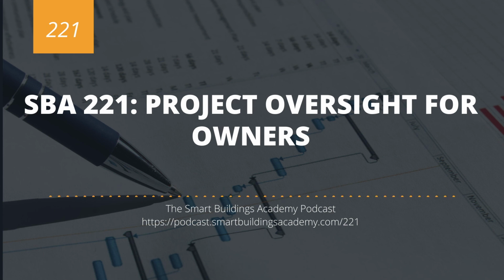That being said, once you understand what is supposed to be done, now you start to go through it. This is where you can request point-to-point documents and you can validate them. You can request functional test sheets and you can validate them. You can work alongside the commissioning agent and validate that systems are actually functioning. This is where I recommend doing document reviews, ensuring that red lines are properly managed and that those red lines are being gathered, properly sourced, and represent what is actually installed in the field.